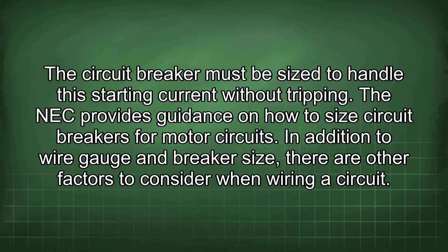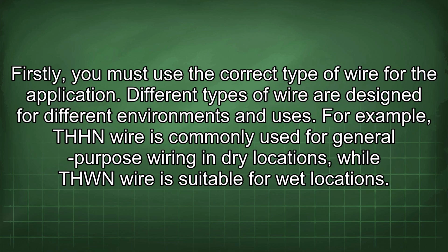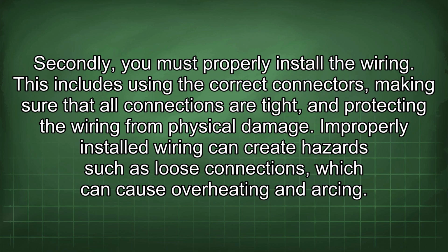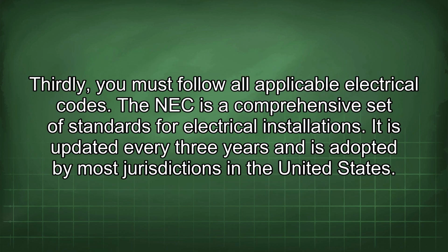In addition to wire gauge and breaker size, there are other factors to consider when wiring a circuit. Firstly, you must use the correct type of wire for the application. Different types of wire are designed for different environments and uses. For example, THHN wire is commonly used for general-purpose wiring in dry locations, while THWN wire is suitable for wet locations. Secondly, you must properly install the wiring. This includes using the correct connectors, making sure that all connections are tight, and protecting the wiring from physical damage. Improperly installed wiring can create hazards such as loose connections, which can cause overheating and arcing. Thirdly, you must follow all applicable electrical codes. The NEC is a comprehensive set of standards for electrical installations.